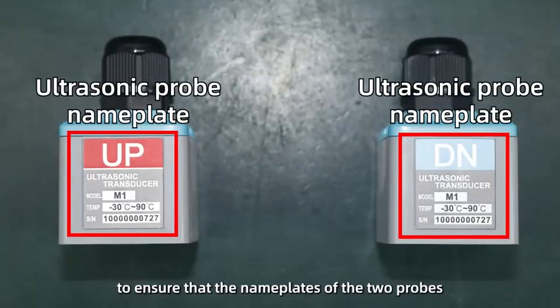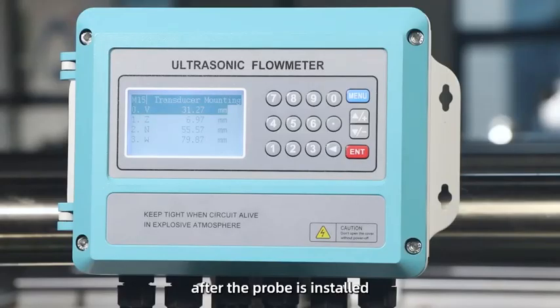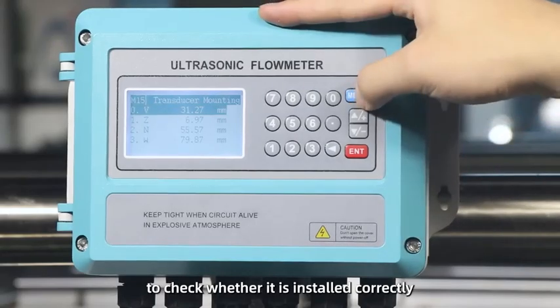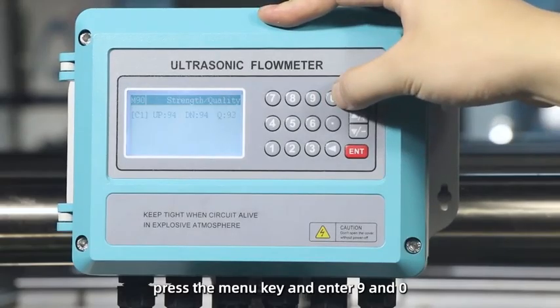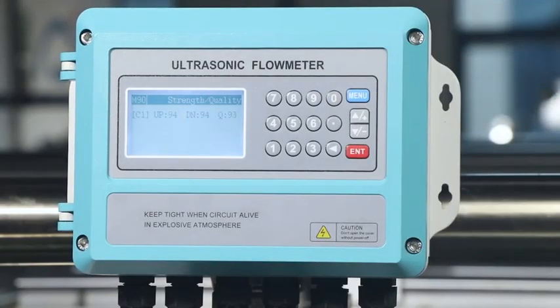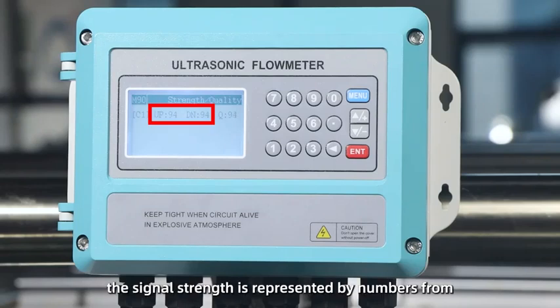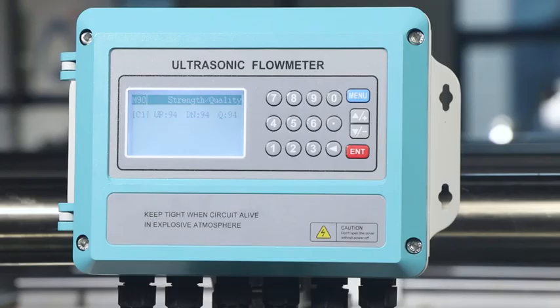Pay attention to ensure that the nameplates of the two probes must be opposite when installing. After the probe is installed, go to the host computer to check whether it is installed correctly. Press the menu key and enter 9 and 0 to enter the M90 window, and observe the signal strength and quality displayed by the host computer. The signal strength is represented by numbers from 00 to 99 after up and DN. 00 means no signal is received, and 99 means maximum signal. The Flowmeter can only measure when the signal strength is greater than or equal to 60.